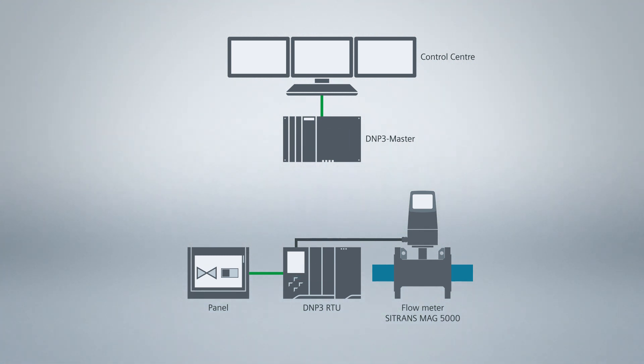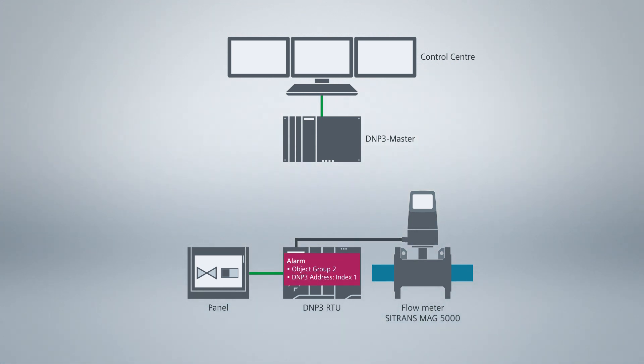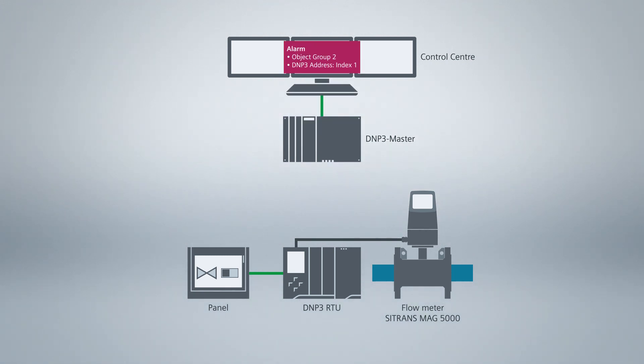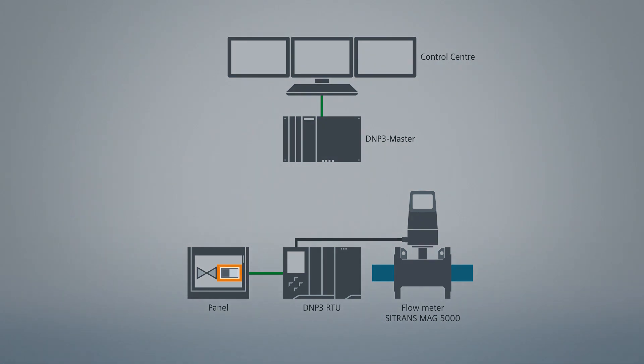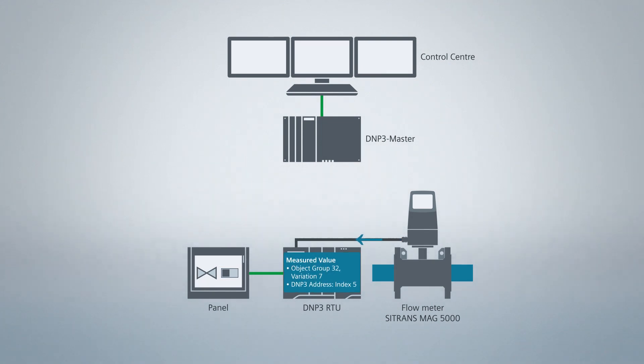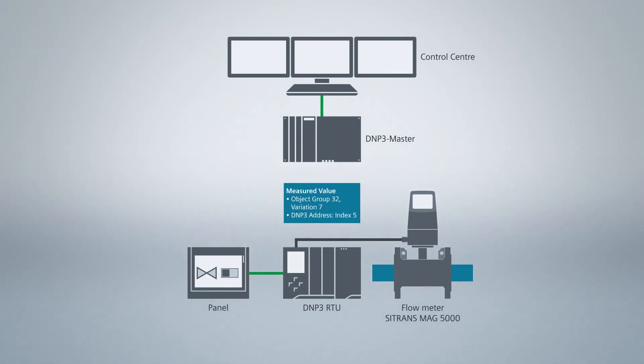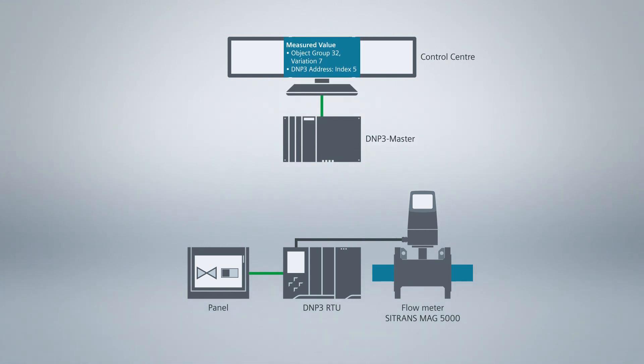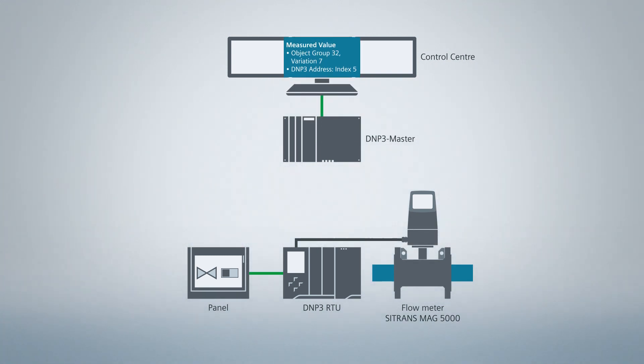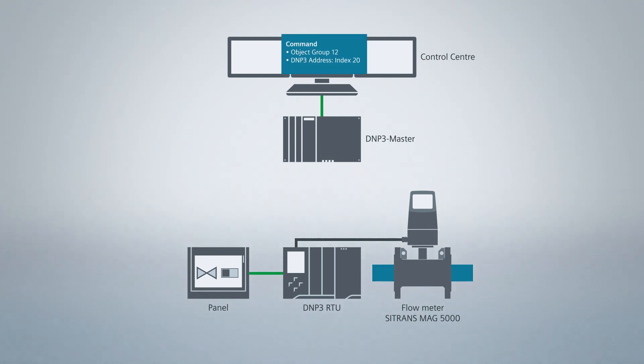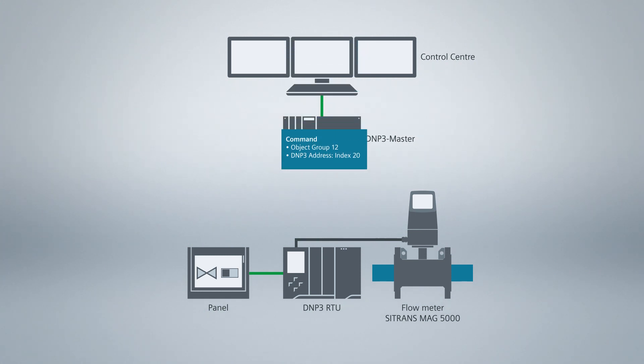Our DNP3 RTU is to transmit an alarm and a measured value to the control center. The alarm is a status information of the type digital input. It is transmitted as object group 2, including timestamp and as an event. The DNP3 address of the object is index 1. I will later simulate the alarm via this button on the panel. The measured value of the flow meter is also transmitted to the master as event, including timestamp. The DNP3 address of the measured value is index 5. Since it is a real value, object group 32 variation 7 is used. The DNP3 master sends a command, object group 12 on index 20 to the RTU.